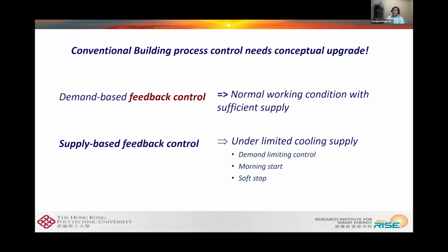But in the future, because our power systems have a high penetration of renewables, the power system supply-demand balance is a big challenge. So they need the demand side to contribute to help keep a healthy balance and to have reliable operation of the power grid. So in many cases, we need to limit our power consumption, and to do so, we need to limit our cooling supply, such as the chiller operation. In such a case, the conventional feedback control system will not work, because it is based on sufficient cooling supply, but with insufficient cooling supply the control logic will not work properly.